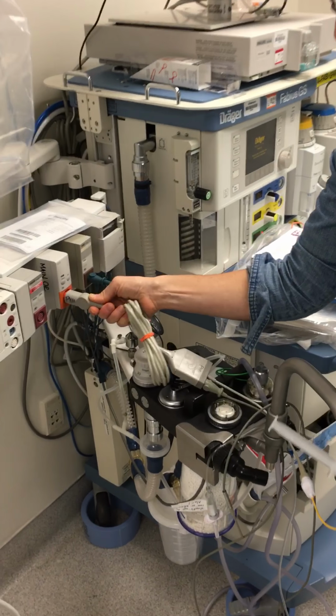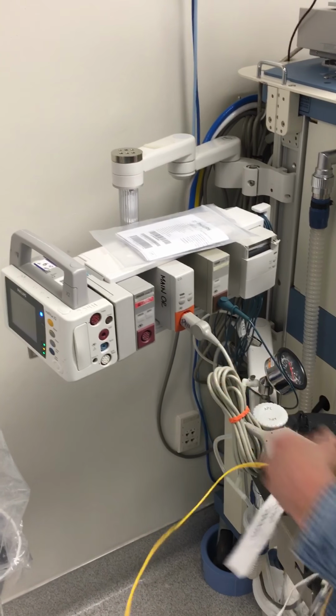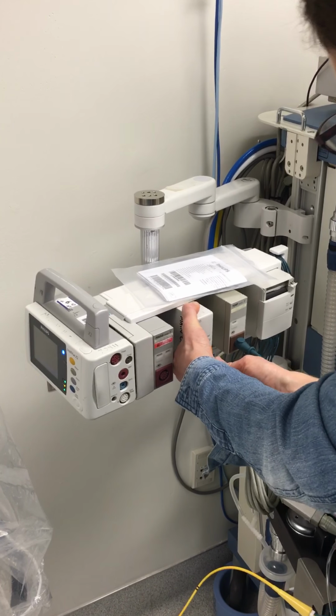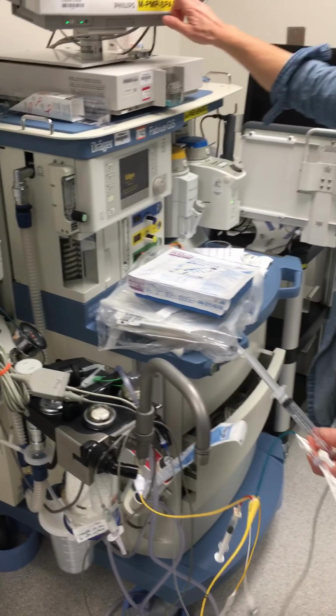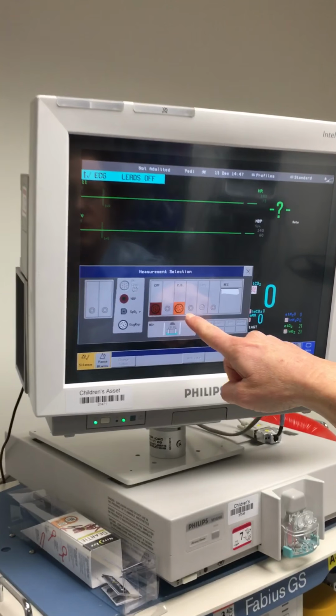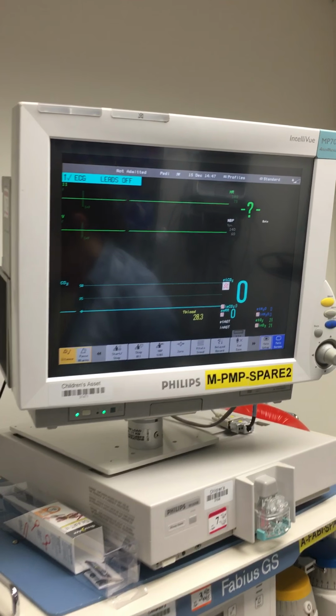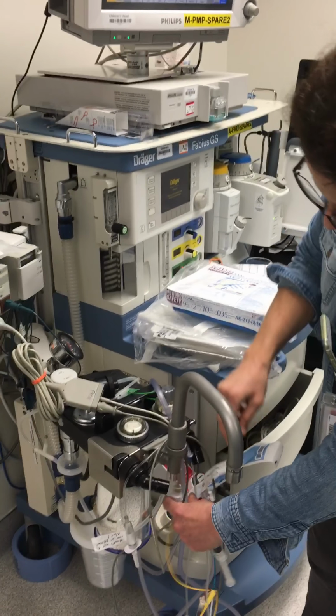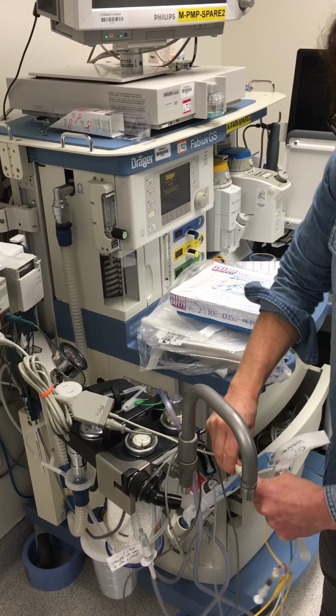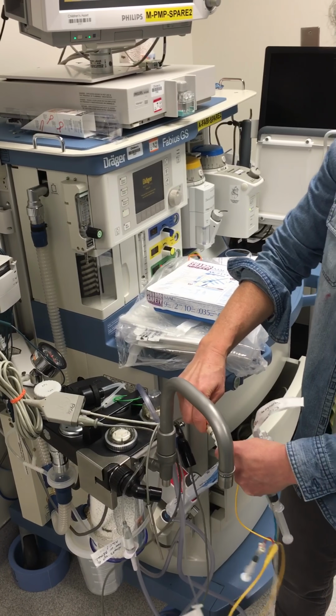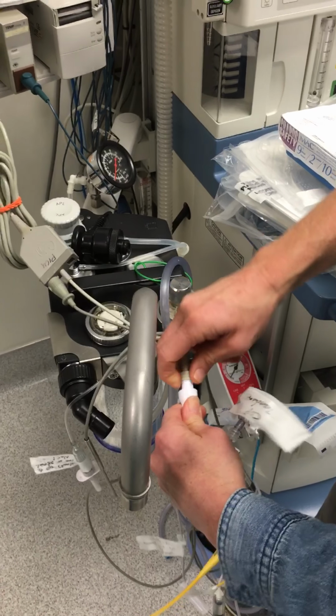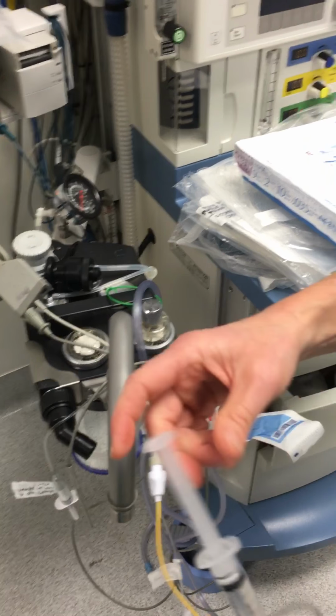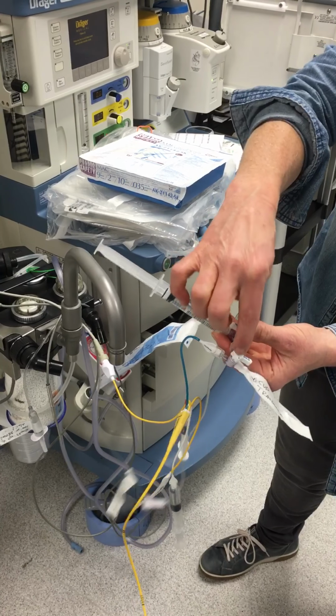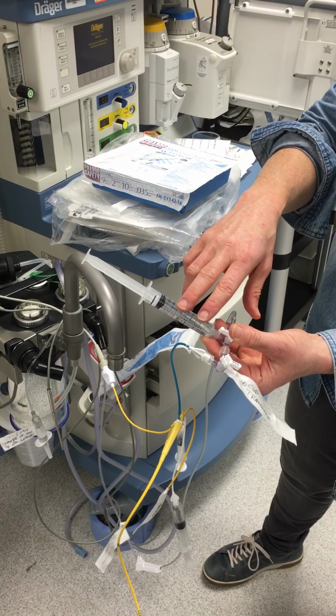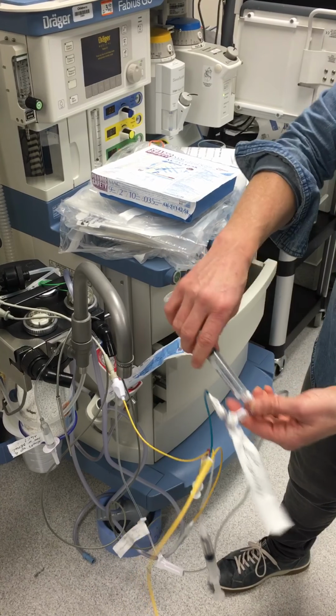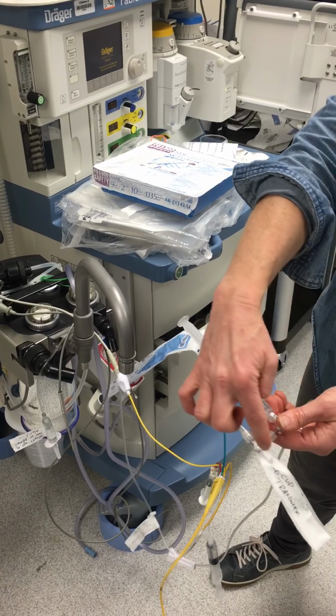But if you do want to shoot cardiac outputs, and certainly in other patients, you'll connect this transducer to this box here that says cardiac output, and it should then be automatically turned on, which it is there. Then this isn't connected yet, so we'll disconnect it. That's how it comes. You will connect this end to here, and it's sort of a luer lock connection. And then this thing here, which is connected to your proximal port, is where you're going to inject your cardiac outputs. While this is off to the cardiac output, it's going to be reading the patient's CVP.